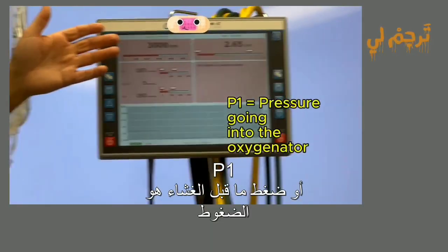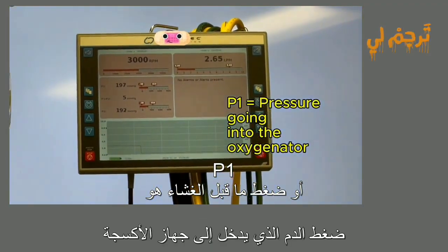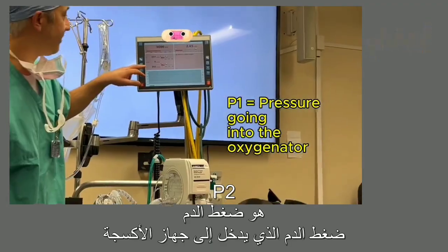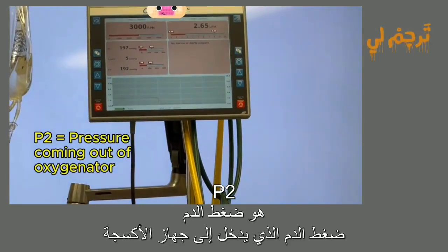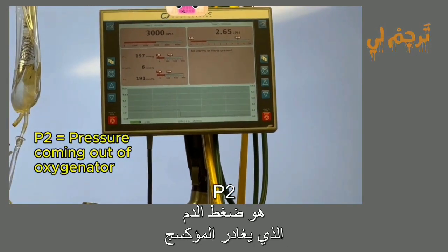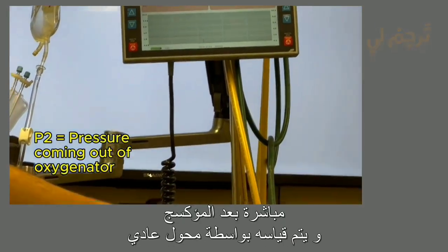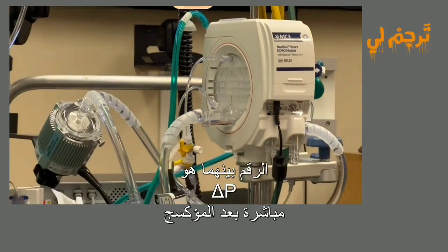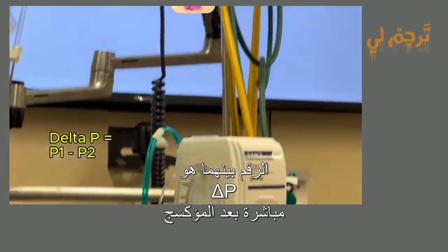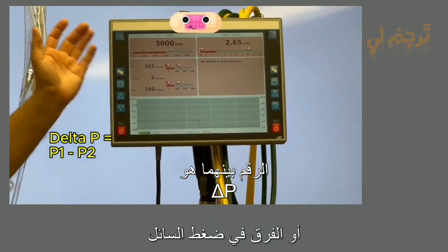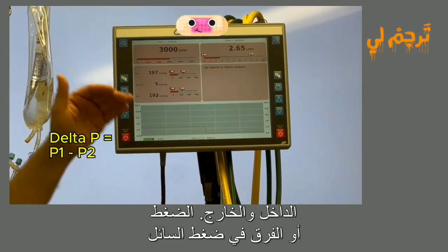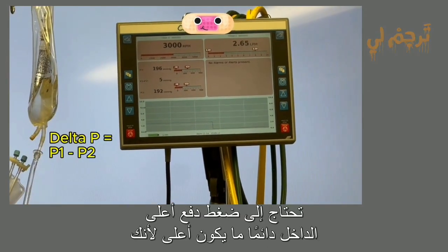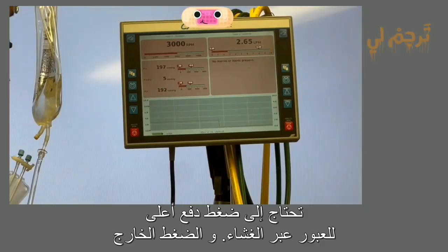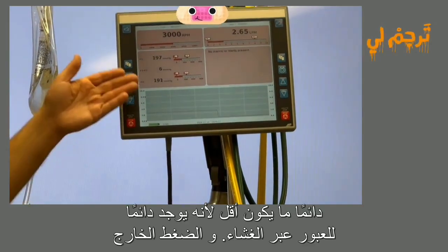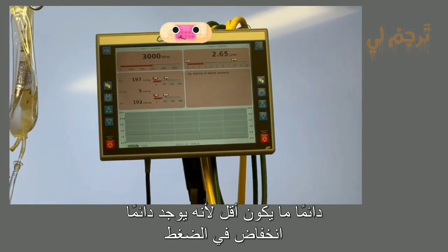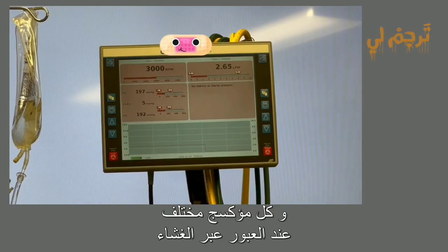P1, or premembrane pressure, is the pressure of the blood going into the oxygenator. P2 is the pressure of the blood leaving the oxygenator, again measured by a normal transducer just after the oxygenator. The number in between is the delta P, or the difference in the pressure going in and coming out. The pressure going in always has to be higher because you need a higher driving pressure to get across and through the membrane. And the pressure coming out is always lower because there's always a pressure drop when you go across the membrane.